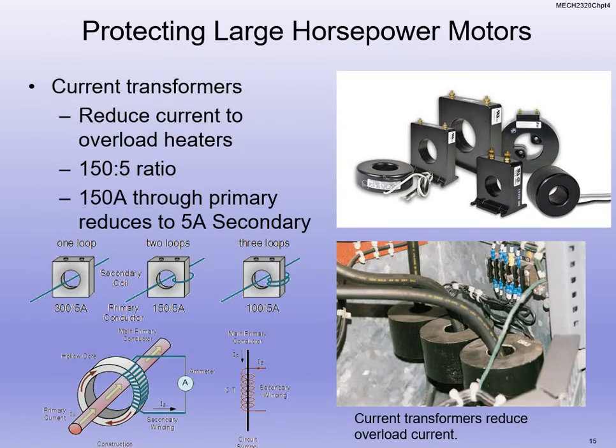So we also have current transformers. A common one that we use is a 150:5 ratio. So we use the primary side of the transformer for 150 amps, and it reduces our secondary to 5 amps. That's how we can really control that inrush current as well. We use this on large horsepower motors, so we're going to use a transformer there. They're very notable, so you can see the picture in the bottom right-hand corner, what the transformer looks like there as it steps down. So we will use a step-down transformer.